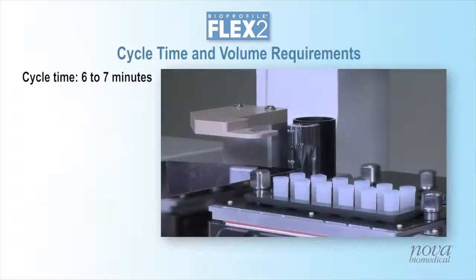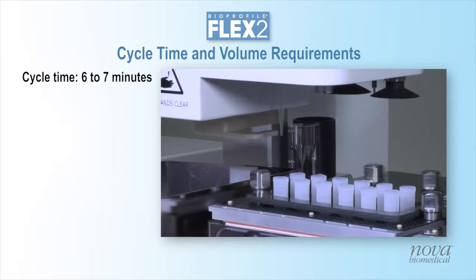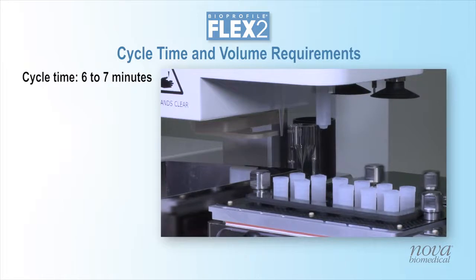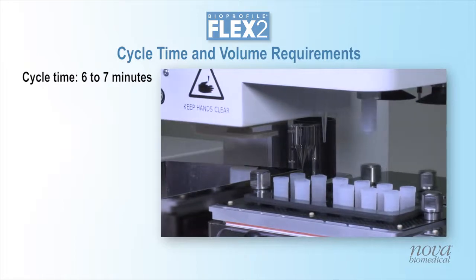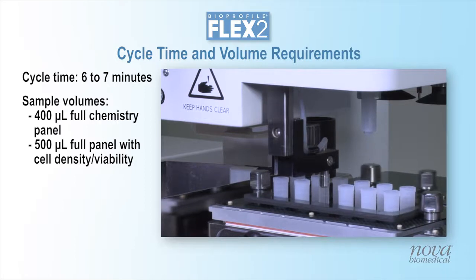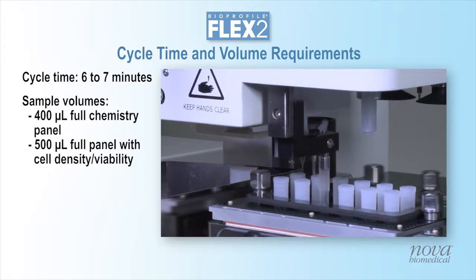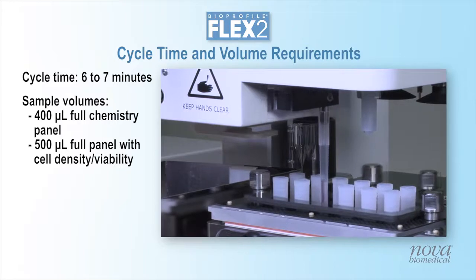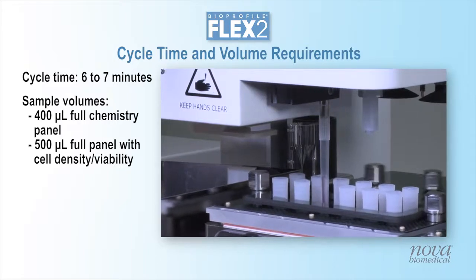The cycle time of the integrated system, including sampling and testing, is 6 to 7 minutes, depending on the configuration of tests selected. Volume preservation is critical for small volume culture systems. The maximum volume taken from each micro-bioreactor is 400 to 500 microliters.